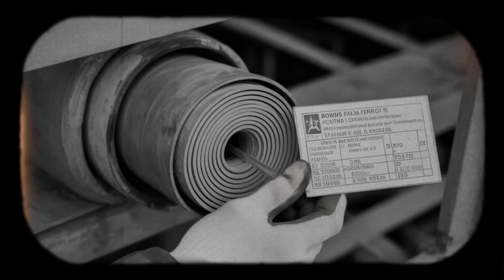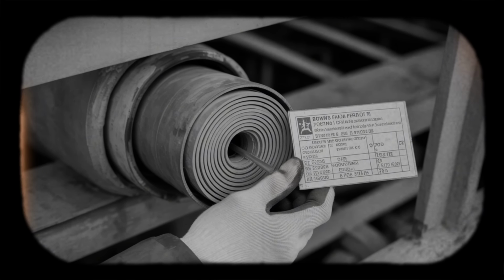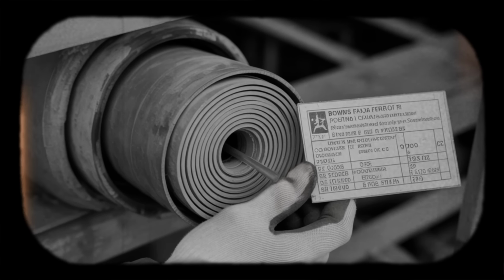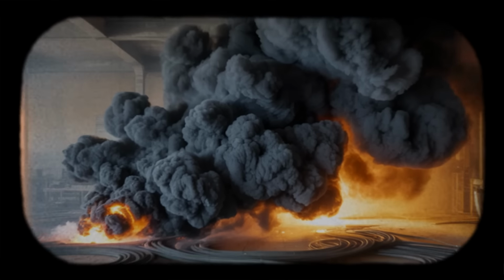The electricians attempt to extinguish the flame. They believe they succeed. The visible flame appears to go out. What they cannot see is the smouldering combustion beginning inside the penetration sleeve, hidden within layers of foam and cable insulation. The ignition draws fire into the wall cavity where hundreds of cables pass through. Polyethylene-insulated conductors begin to heat. Insulation softens. The fire finds continuous fuel.